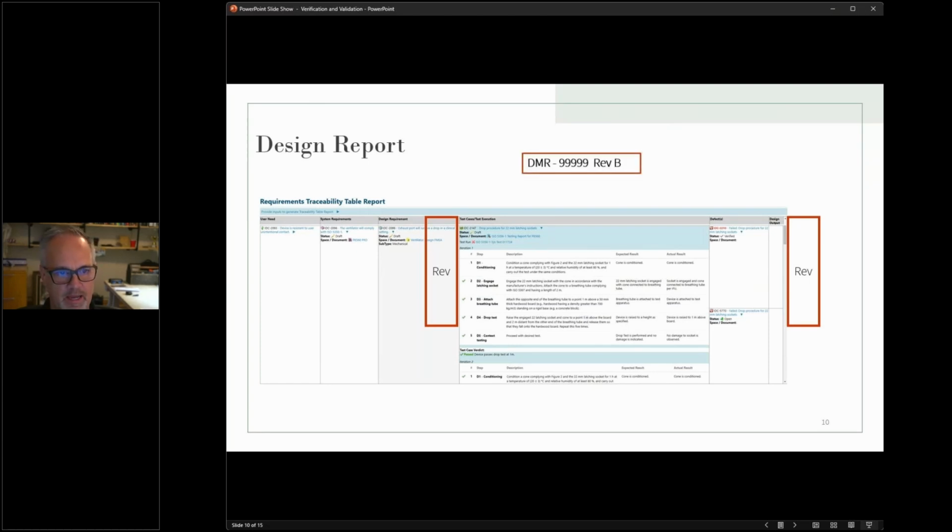And of course, what we'd like in this report is to be able to establish what is the DMR we're concerned with, what's the revision of the DMR, have it pull up the outputs, and then tell us whether the testing is approved for that version of the DMR so that we have a checkoff that says we have all the testing in place, not just for this product, but for the revision of the DMR that we're concerned about approving for shipment.